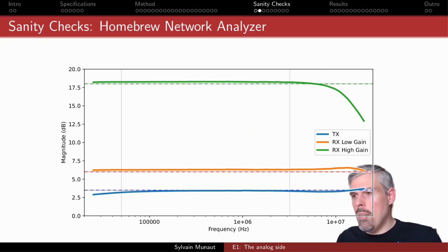That worked very well. But we can see that on the receive high gain, there is a frequency roll-off at higher frequency for sure, when we get to like 10 megahertz. The 3 dB point would be 15 dB, which would be around here, around 15 megahertz or so. But it's way above what we're testing, so it's fine.